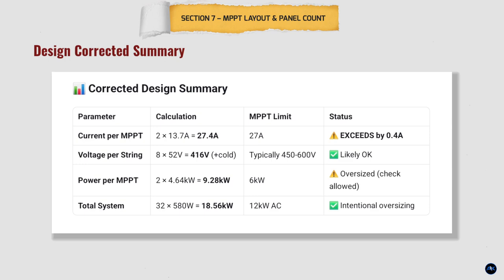Parameter, calculation, MPPT limit, status. Current per MPPT is 2 times 13.7 amps equals 27.4 amps. The MPPT limit is 27 amps, and we have a caution sign. It exceeds by 0.4 amps. Voltage per string is 8 panels times 52 volts equals 416 volts, plus cold temperature. The typical limit is 450 to 600 volts, and this is likely okay. Power per MPPT is 2 times 4.64 kilowatts equals 9.28 kilowatts. The MPPT limit is 6 kilowatts, and this is oversized, and we must check allowed buffer. Total system is 32 panels times 580 watts equals 18.56 kilowatts. The AC limit is 12 kilowatts, and this is intentional oversizing.